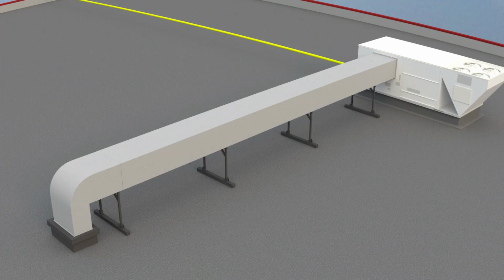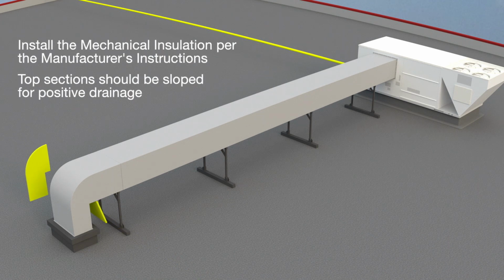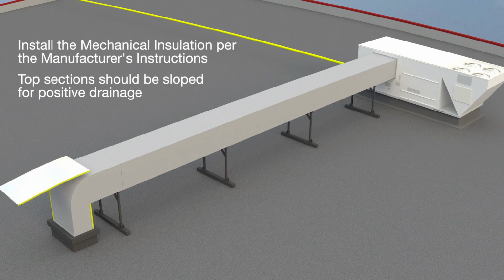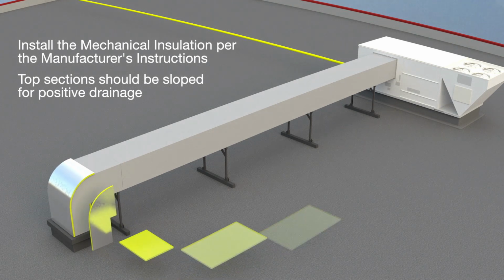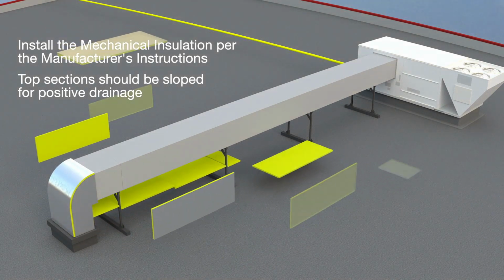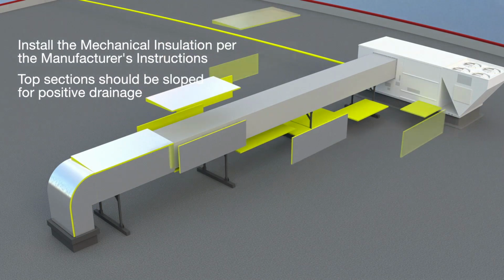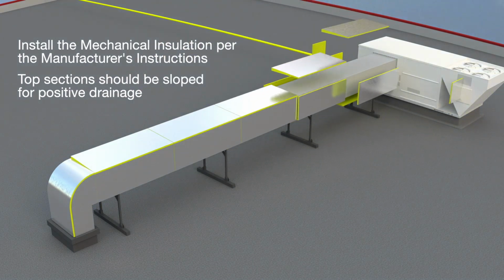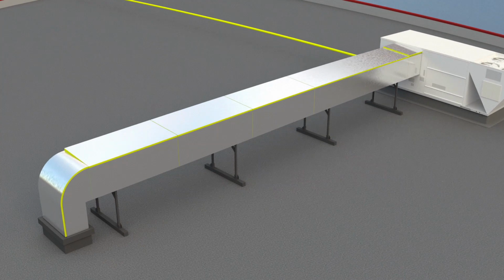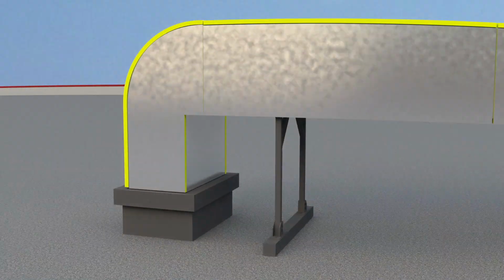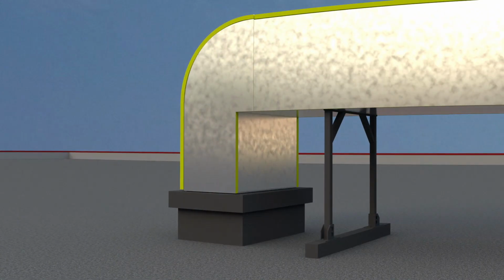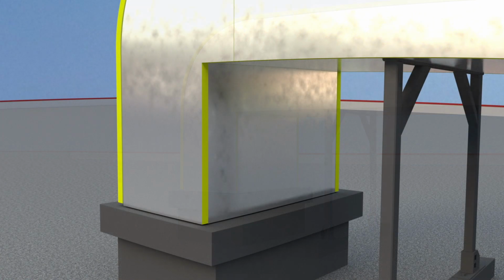This project is starting with the installation of the mechanical insulation with a foil facer. FlexClad can be installed directly to the ductwork or piping, or over insulation such as polyiso, fiberglass, EPS, or extruded polystyrene board. Each type needs a foil or film facer for proper adhesion. Once the insulation is installed, start installing FlexClad at the lowest point of the ductwork.